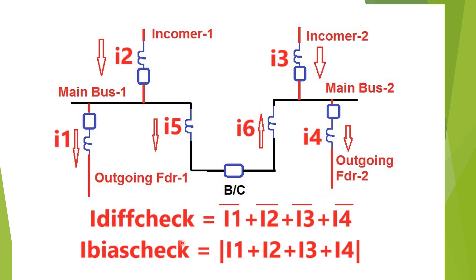For the check zone, i_diff_check is the vector sum of all currents flowing towards and outside the bus — i1 (outgoing feeder one), i2 (incomer one), i3 (incomer two), and i4 (outgoing feeder two). The bias current for the check zone is the scalar sum of these four currents.